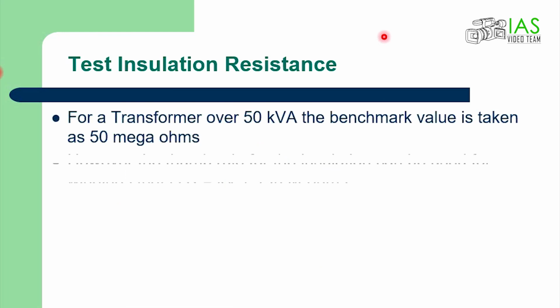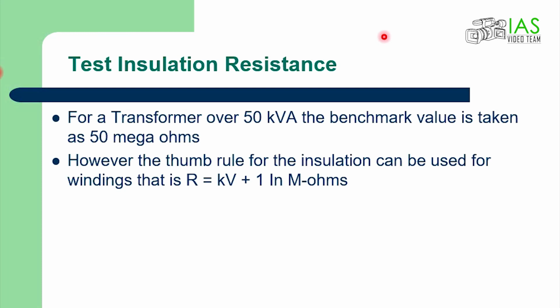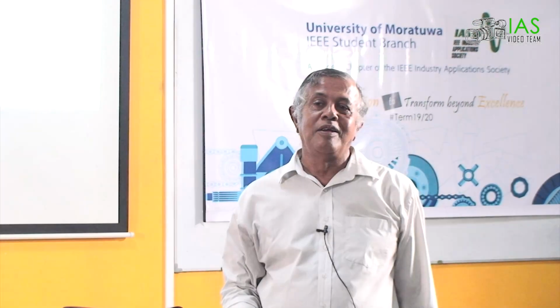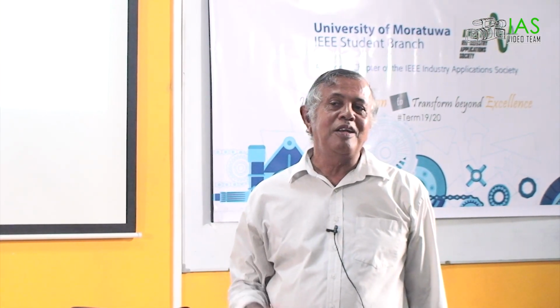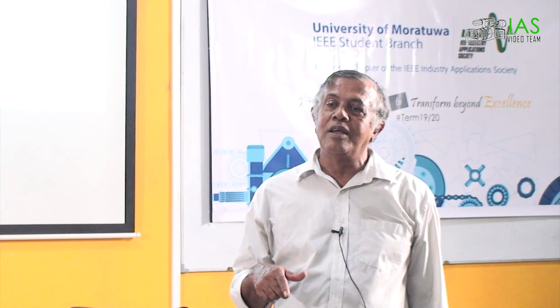So insulation resistance, normally over 50 kVA, the benchmark value is taken as 50 mega ohms. And in ASTM, it says the insulation resistance value R can be kV plus 1. For 132 kV, then it becomes 133 mega ohms, right? And for 33 kV, it becomes 34 mega ohms, like that.